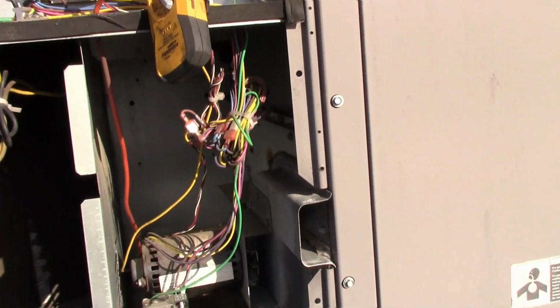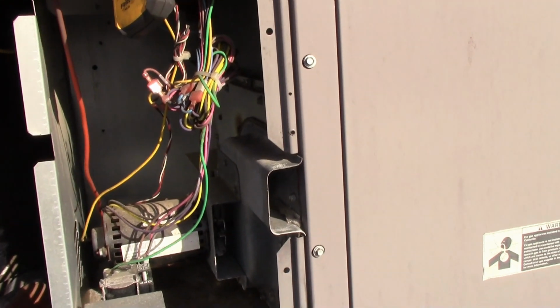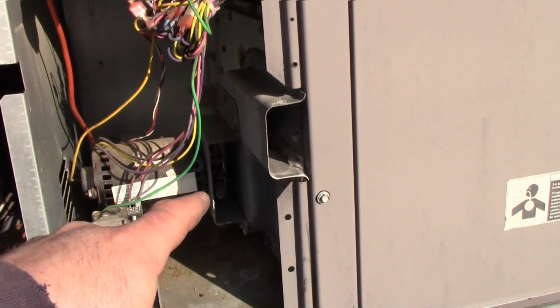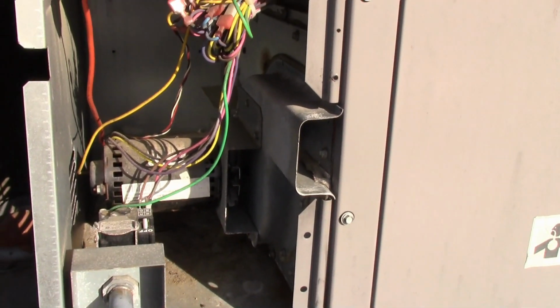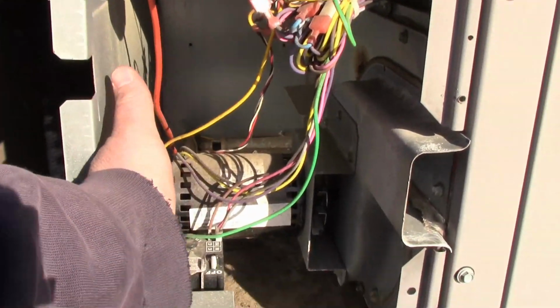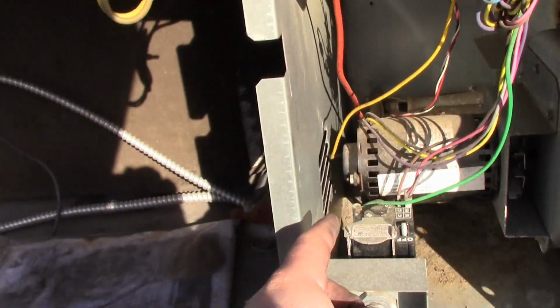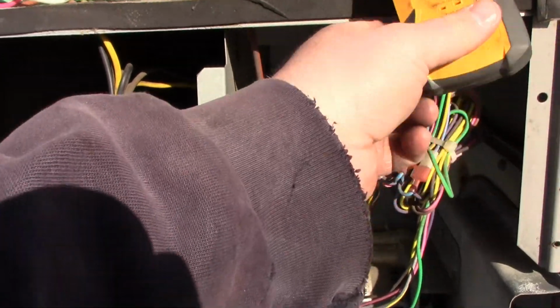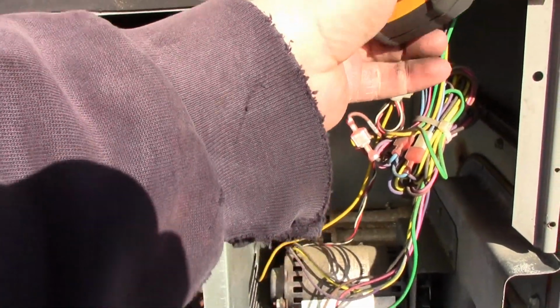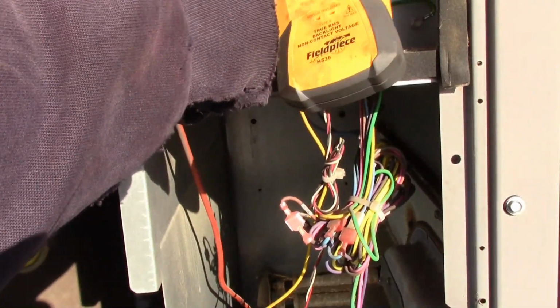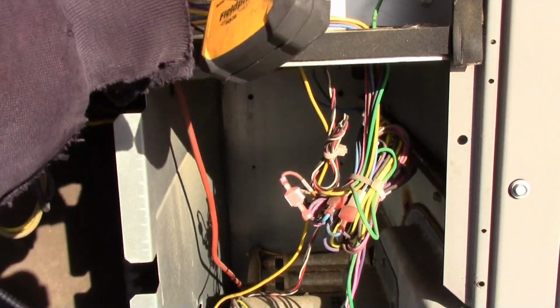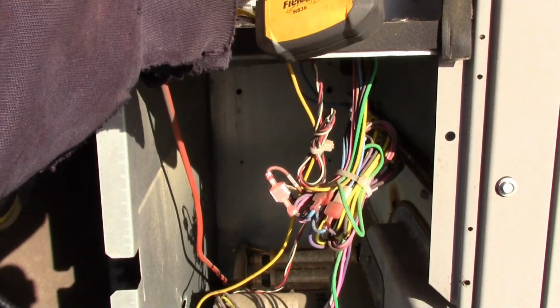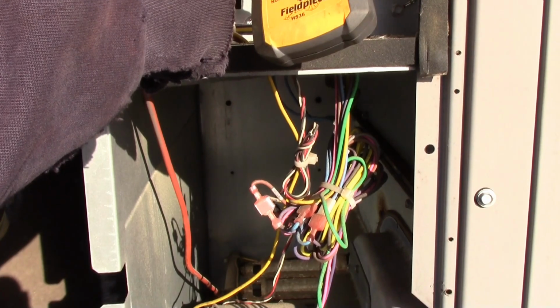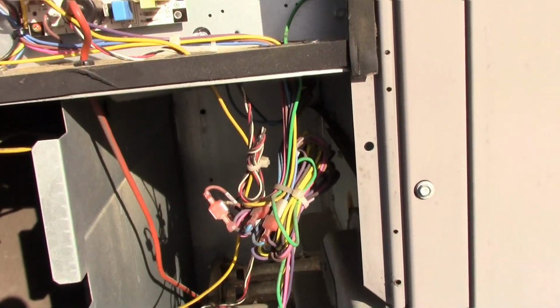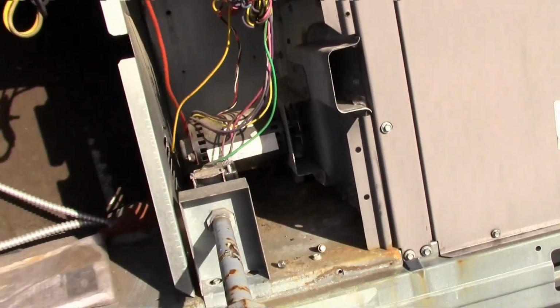So first thing that'll happen, there might be a delay because those are digital thermostats, but once we get the call for cooling, or heating rather, this draft motor will turn on. Then once it sends a signal from this Hall effect sensor right here to the board that the motor's turning, it'll turn on. So right now my blower's on. I'm reading 2 amps, so we're good and we're nice and tight.